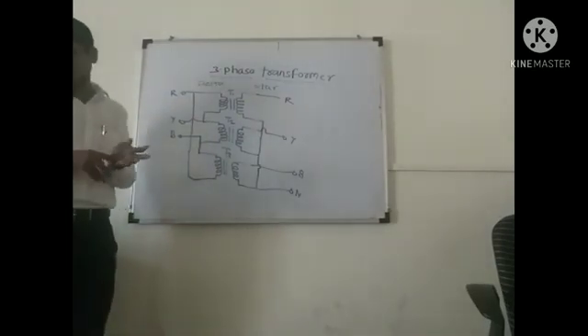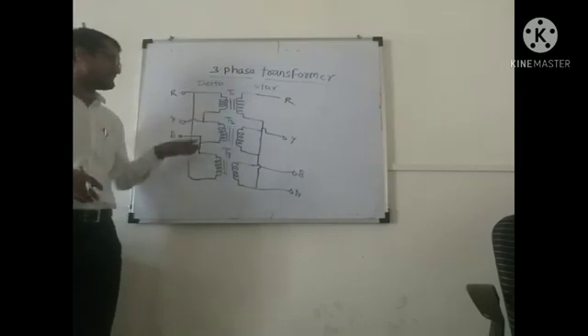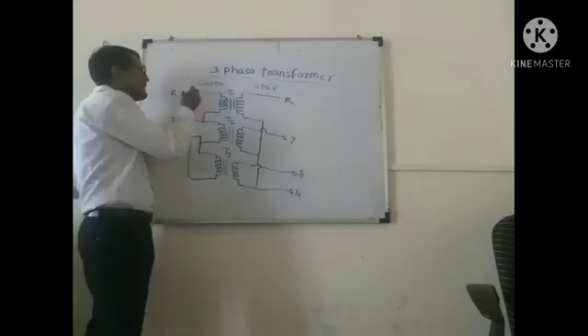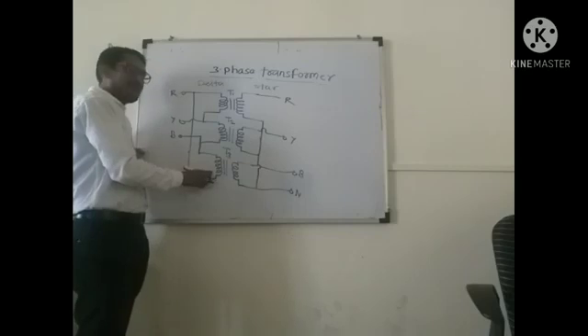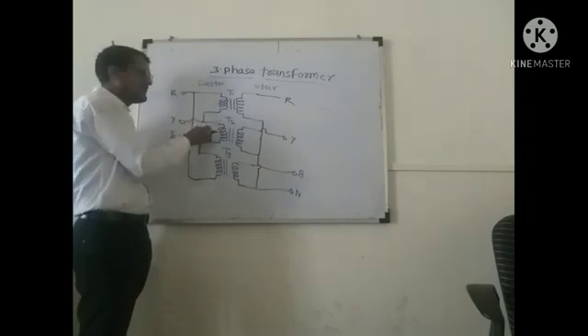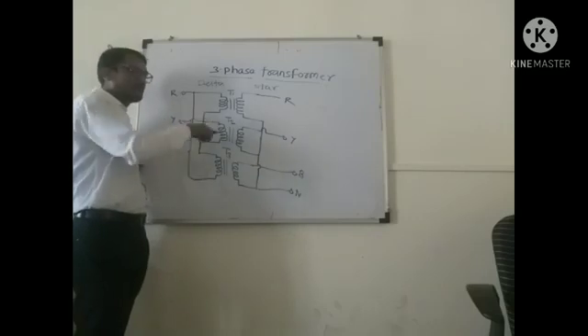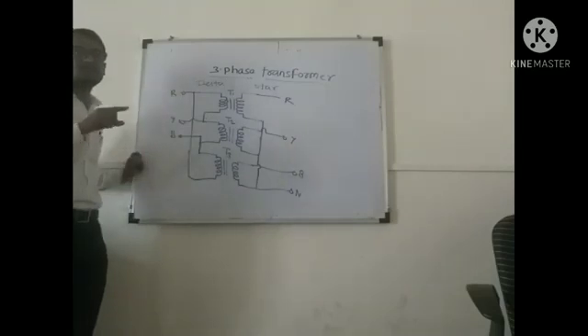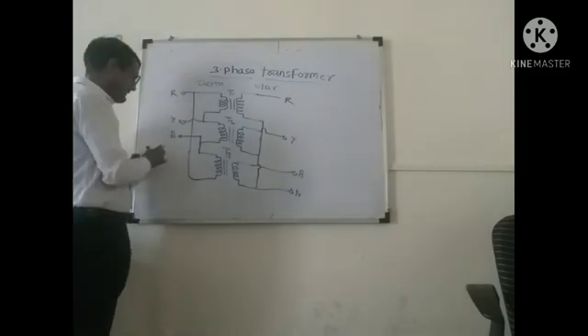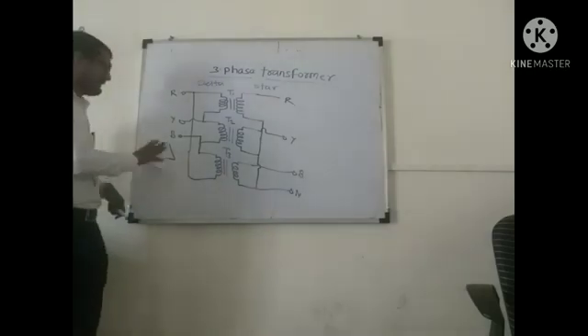Here we observe transformers T1, T2, and T3 — three single units of single-phase transformer. The first terminal of the first transformer is connected to the second terminal of the third transformer. The second terminal of the first transformer is connected to the first terminal of the second transformer, and the second terminal of the second transformer is connected to the first terminal of the third transformer. This forms a triangle shape of winding, because of that we call it a delta connection.